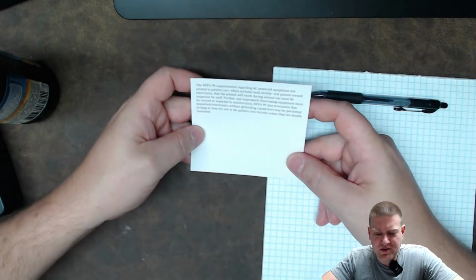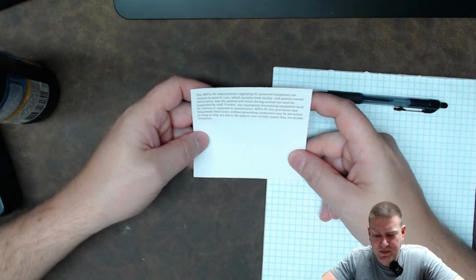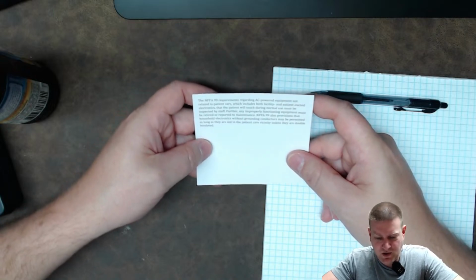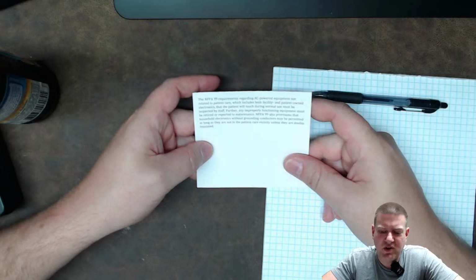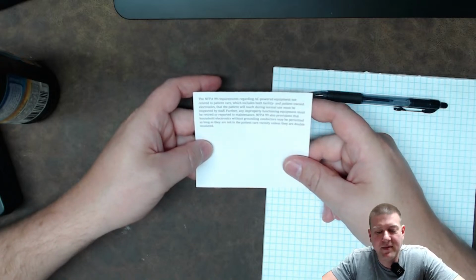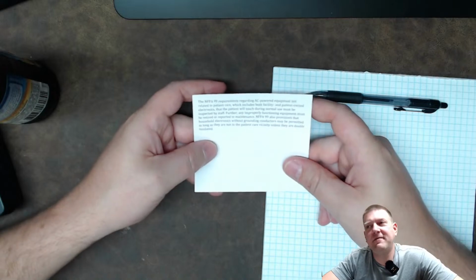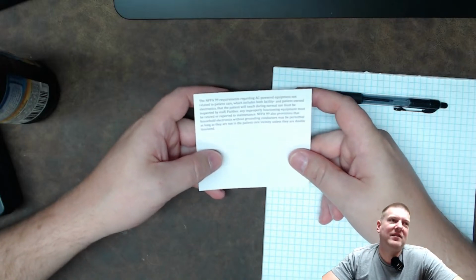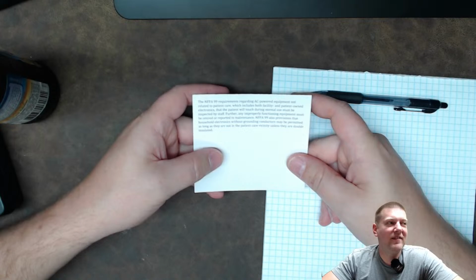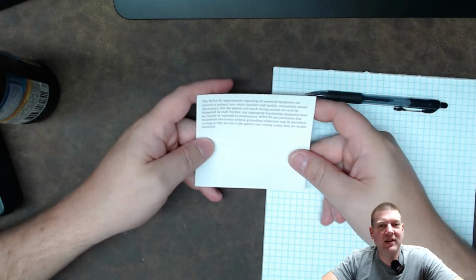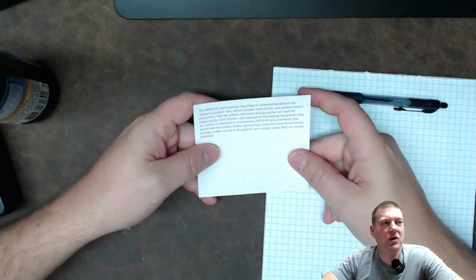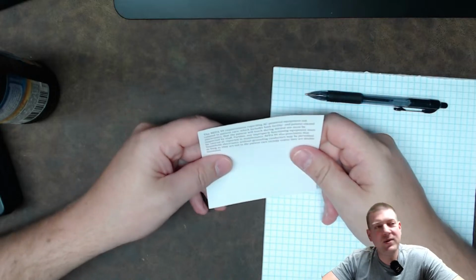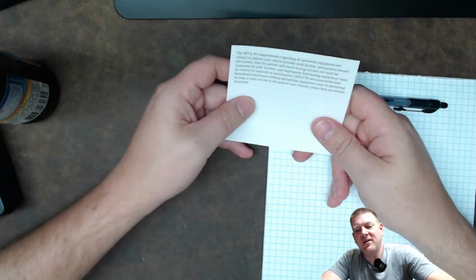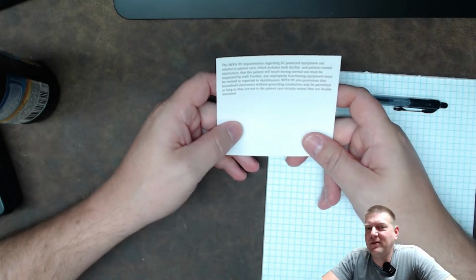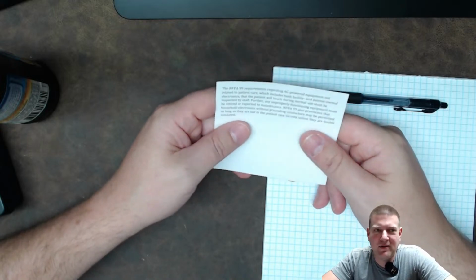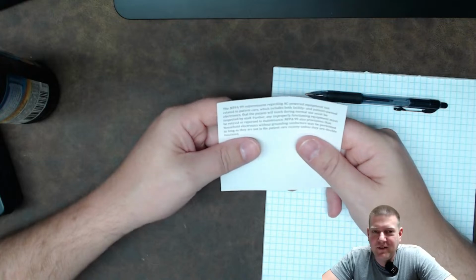NFPA 99 requirements regarding AC-powered equipment not related to patient care, which include both facility and patient-owned electronics that the patient will touch during normal use, must be inspected by staff. It says just inspected by staff. It does not say inspected by biomed, all right? There's a lot of people out there in this industry who think that biomed has to inspect every single toaster that comes in the door. We do not, okay? And that includes like the CPAP machines and stuff. Do not touch them if you don't have to. I mean, trust me. If you touch it, you own it.